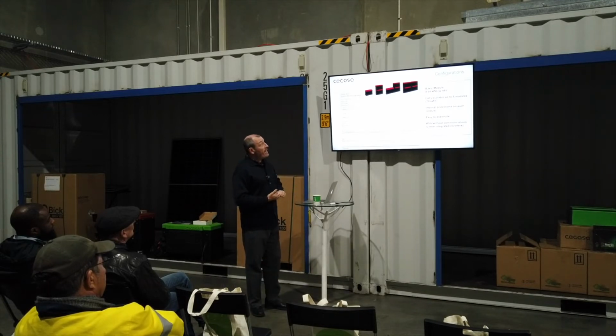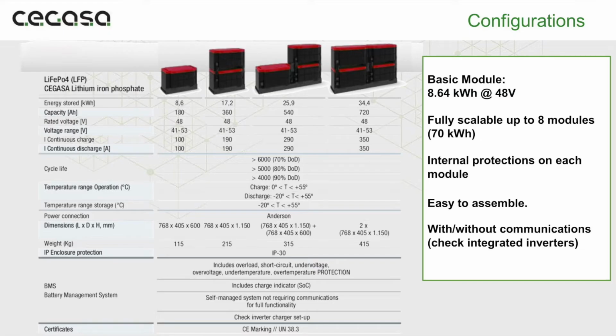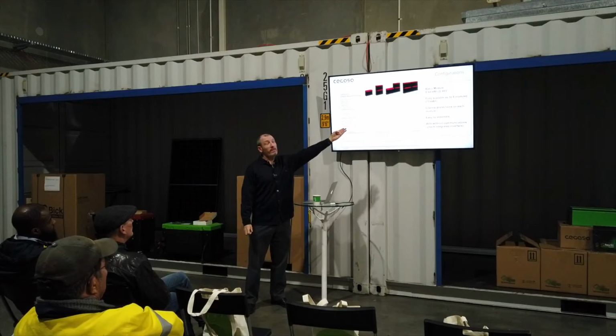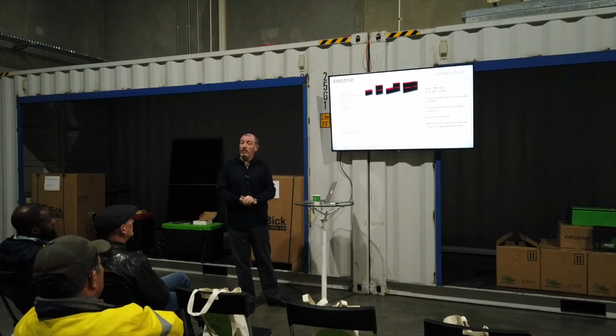One characteristic here is that we haven't set a limit for the current. So the moment you are connecting the Ultras in parallel, not only are you increasing the capacity accordingly, but also the continuous charge and discharge that it is able to hold. Which means that in many of the applications we find here in Australia, especially off-grid, they might have engines, they might have pumps, they might have things connected. They need an extra punch of current, an extra peak of current. Well, the moment you connect 3-4 modules, you get to a decent current that can hold all this.